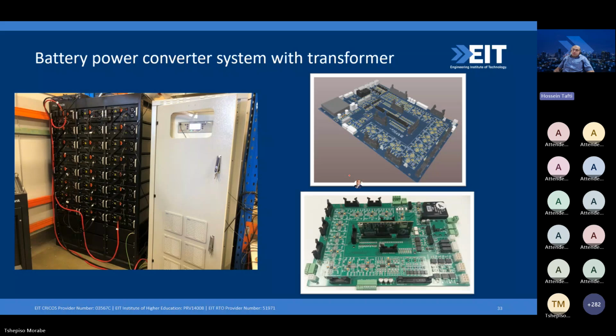A quick look at a real system, a battery system that you can see here on the left. That's a battery system from a company called Pylon Tech, and it consists of many battery modules. You can see these small modules at each rack; they are called one battery module, each rated at about 24 volts. In order to create a DC bus of 1000 volts, we needed to install many of them in series. On the side, you can see a battery inverter.